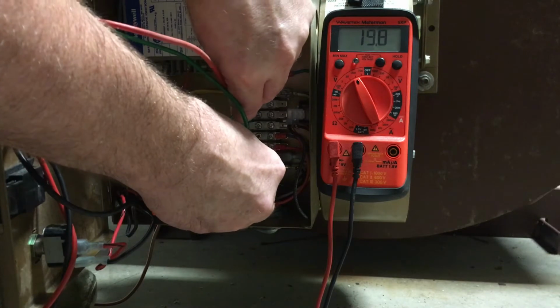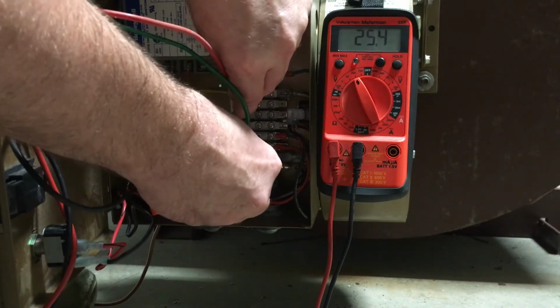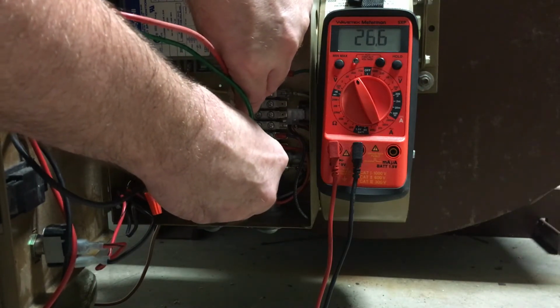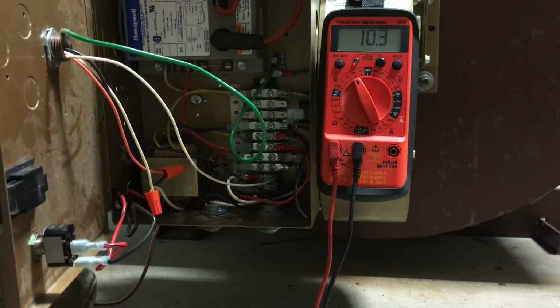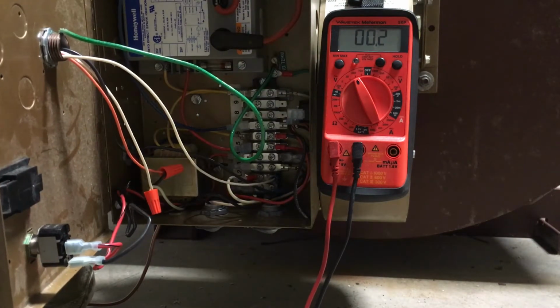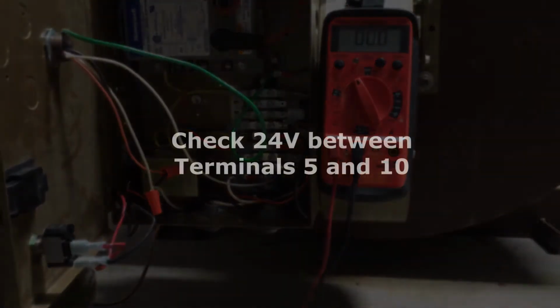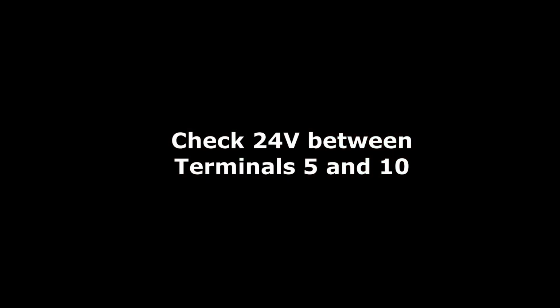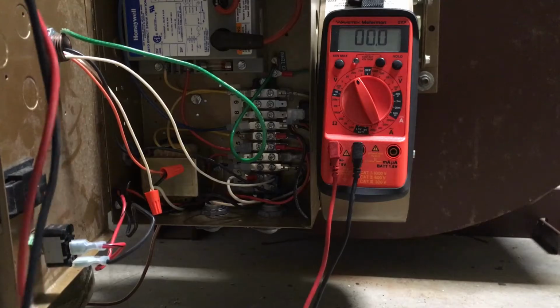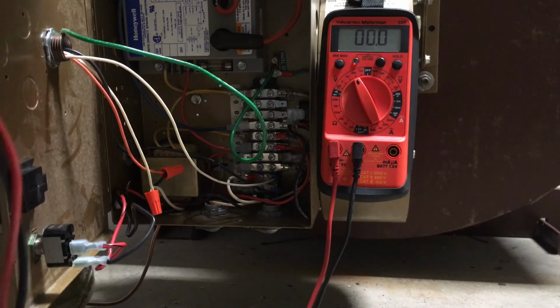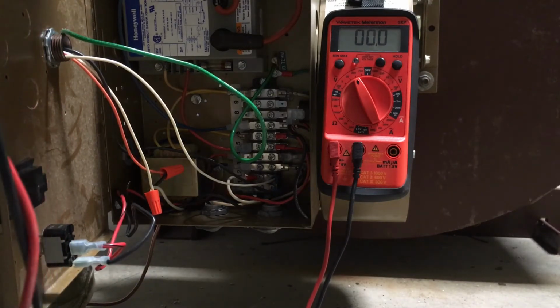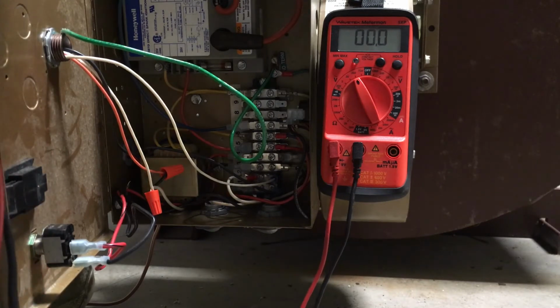And 10. You see, we are getting 25, 26 volts. So now that transformer is operating properly. So we will go to the next step, which is checking the 24 volt between terminals 5 and 10.